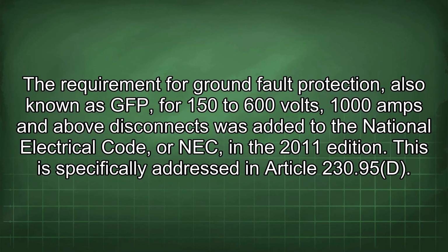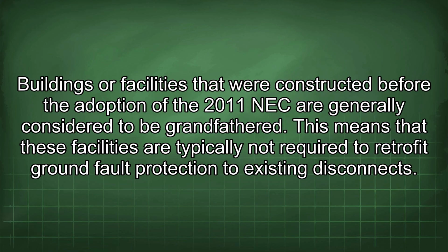The requirement for ground fault protection, also known as GFP, for 150 to 600 volt, 1000 amp and above disconnects was added to the National Electrical Code, or NEC, in the 2011 edition. This is specifically addressed in Article 230.95(D). Buildings or facilities that were constructed before the adoption of the 2011 NEC are generally considered to be grandfathered. This means that these facilities are typically not required to retrofit ground fault protection to existing disconnects.